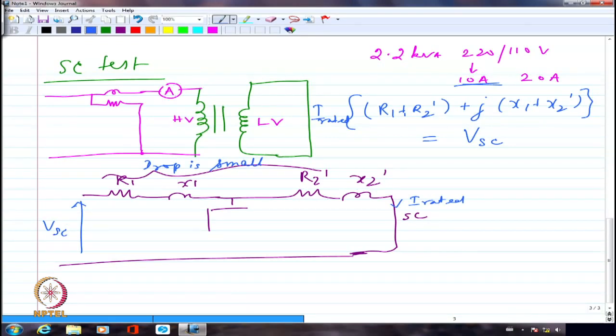Whether I look at the primary or secondary, if I limit the current to rated value, both of them will be limited to rated value. Okay? So I am going to have essentially the voltage applied during the short circuit test to be much, much lower than the rated value of voltage. So under short circuit test, whatever is the voltage I apply, indirectly it gives me an indication of what are the internal impedances of the winding of the transformer. It gives me a feel for what is R1 plus R2 dash, what is X1 plus X2 dash. So if the voltage applied during short circuit test is only 10% of the rated value, that means the voltage drop that is taking place within the transformer winding is only 10% of the rated voltage. If it is 5%, that means I have even lesser amount of impedance internally within the transformer. So the voltage drop becomes less and less.